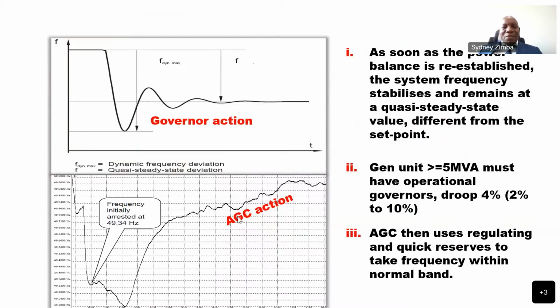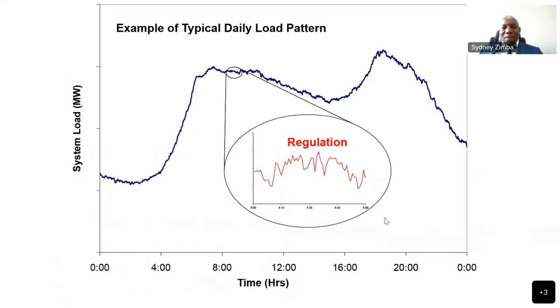And this regulating reserve uses AGC. It's normally centralized from your national control center. You send the commands to your power plants to regulate, to pick up, to cover for the slow but regular short changes, like these ones. So you'll be having short changes. These are now contained by the regulating reserves. This is an example of a typical daily load pattern, our peak being around 18 hours, then there's another morning one around 7 hours.